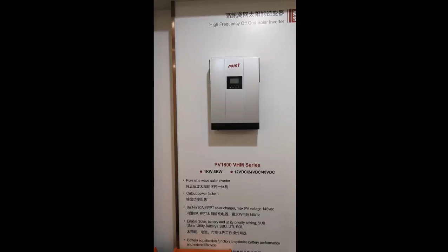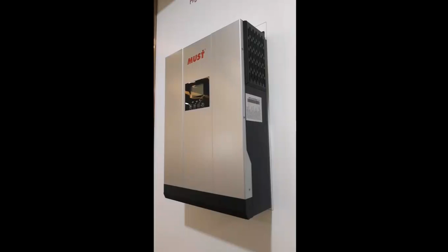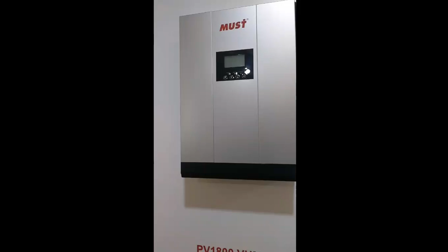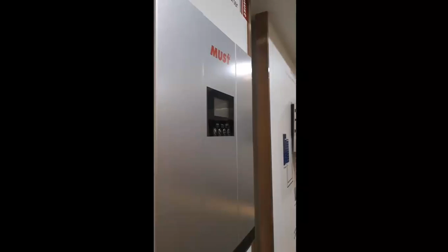And the next series is the PV1800 series. For this series, we have VHM, VPM, VPK, which means it has the MPPT solar charge controller inside or without the MPPT solar charge controller inside. The power range is from 1 kilowatt to 5.5 kilowatts. And the latest power factor is 1. It has built-in 80 amps and 60 amps MPPT for the inverters, and has the battery equalization function to optimize battery performance and extend the life cycle.